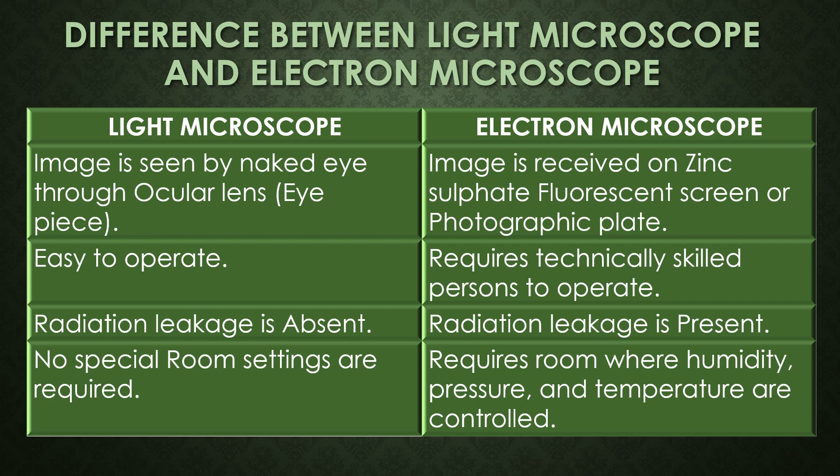In the electron microscope the image is received on a zinc sulphate fluorescent screen or a photographic plate. The light microscope is easy to operate, but the electron microscope requires a technically skilled person to operate. Radiation leakage is absent in the light microscope but present in the electron microscope. The light microscope does not require special room settings, but the electron microscope requires a room where humidity, pressure, and temperature are controlled.